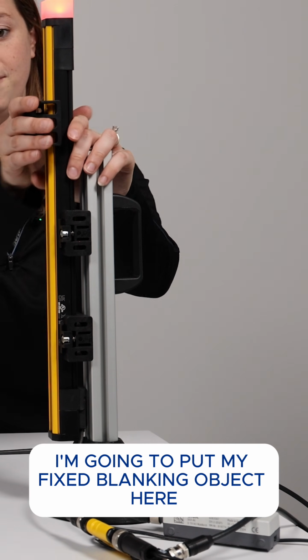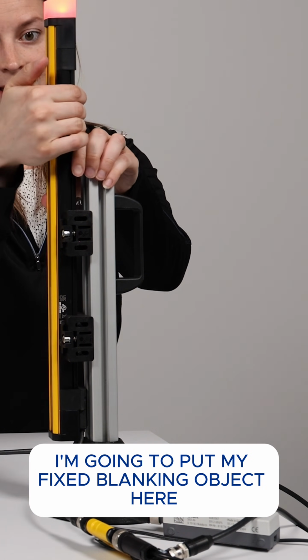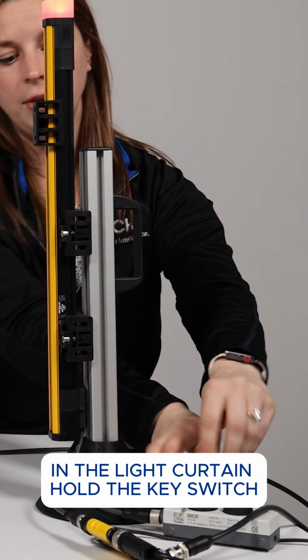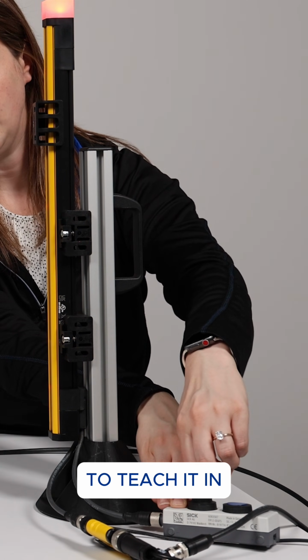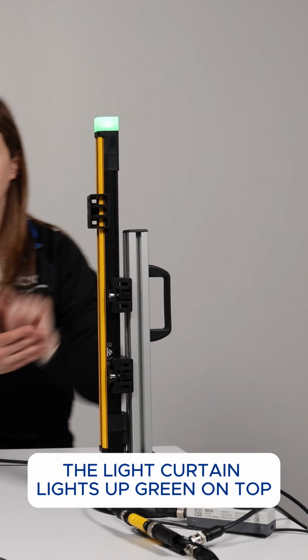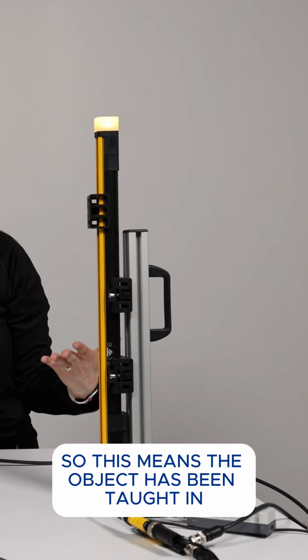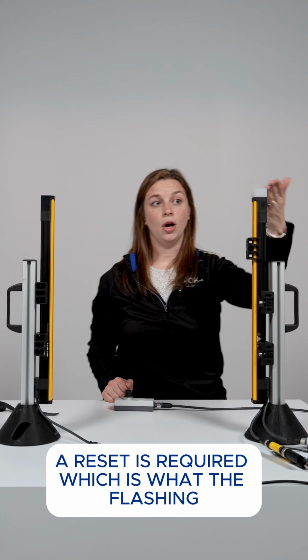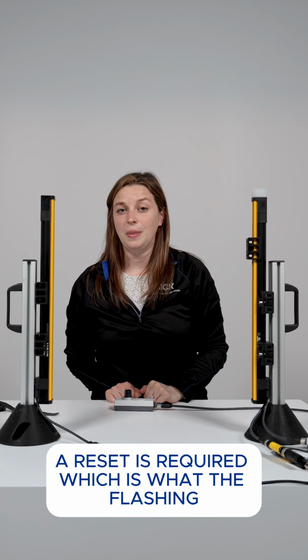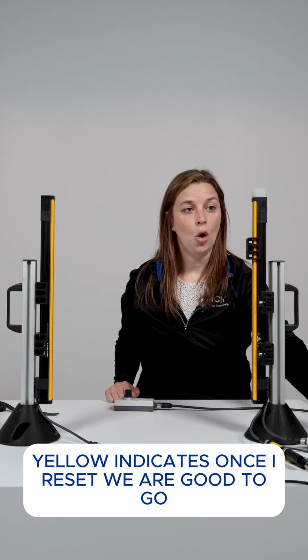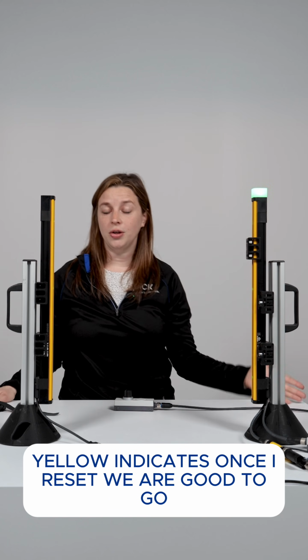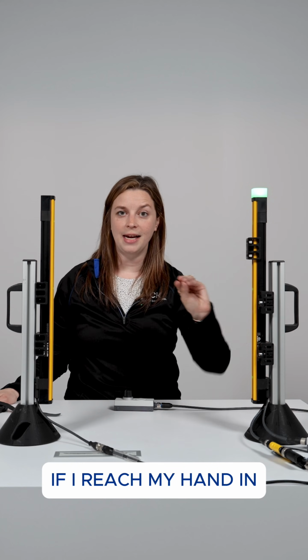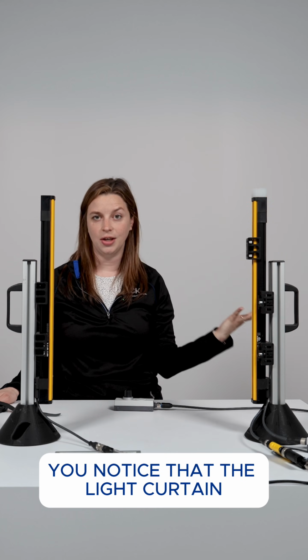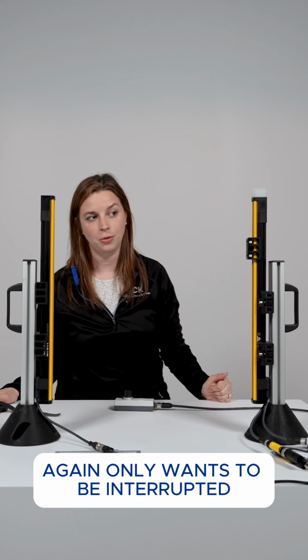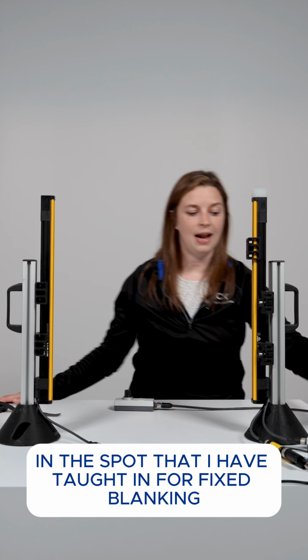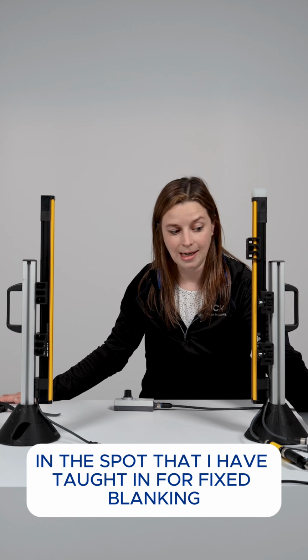I'm going to put my fixed blanking object here in the light curtain, hold the key switch to teach it in. The light curtain lights up green on top, so this means the object has been taught in. A reset is required, which is what the flashing yellow indicates. Once I reset, we are good to go. If I reach my hand in, you notice that the light curtain, again, only wants to be interrupted in the spot that I have taught in for fixed blanking.